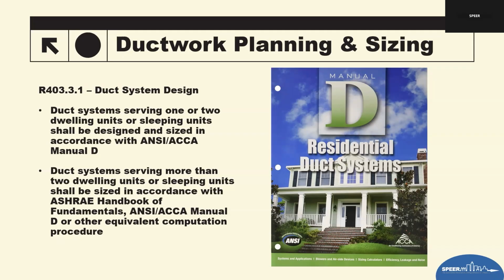So for systems serving apartments, condos, sleeping units, and multifamily buildings, designers can use Manual D and/or recognized engineering methods such as the ASHRAE Handbook of Fundamentals or other approved computational methods. That would be approved by the building official if they deem that it satisfies the requirement. This flexibility is mainly because multifamily HVAC varies more and has more requirements for commercial design tools. So plan reviewers, if you're on here, should also verify that the full Manual J, S, and D package is submitted, not just a duct drawing.